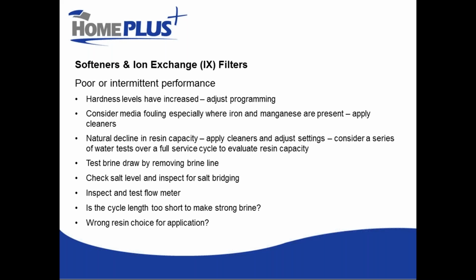There's usually a flow meter, like I said, associated with this type of equipment. Make sure that flow meter is clean as well and operating correctly. Most softeners show on the screen, when you're running water, a countdown of the number of gallons remaining until the next regeneration cycle. If you're running water and you don't see that counting down, you probably have a problem with that flow meter. So you can take a look at that.